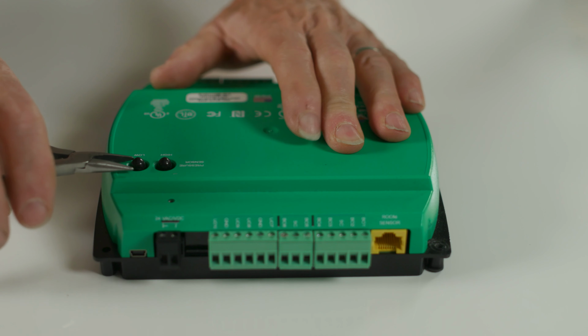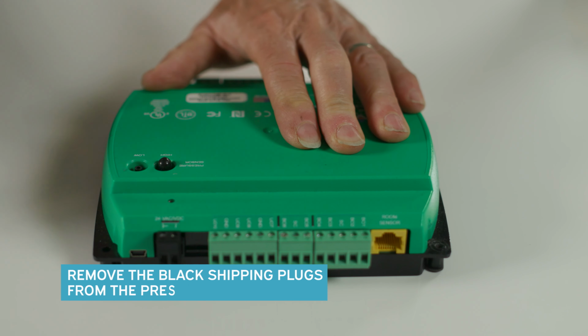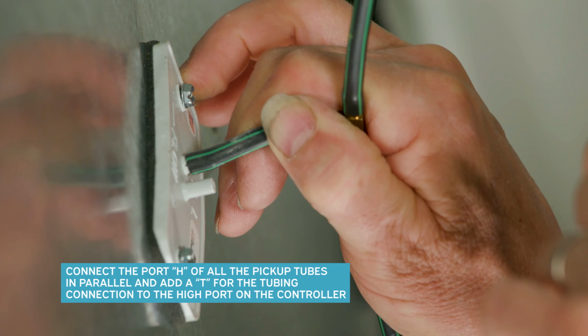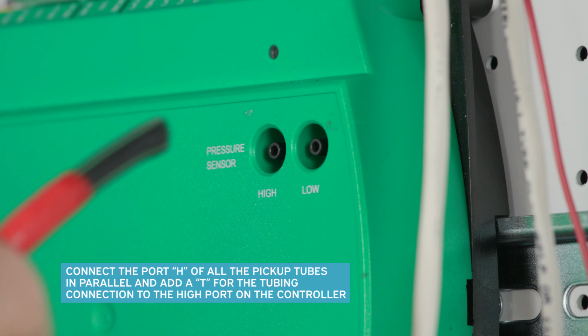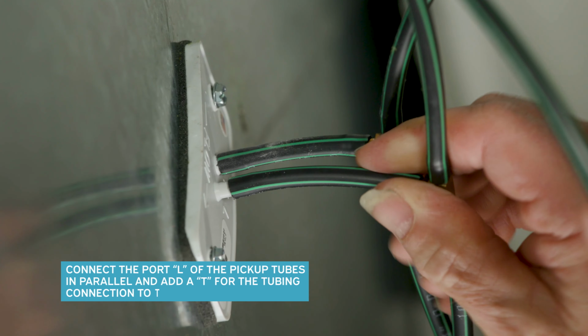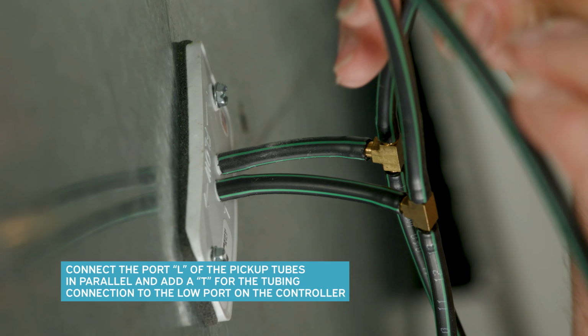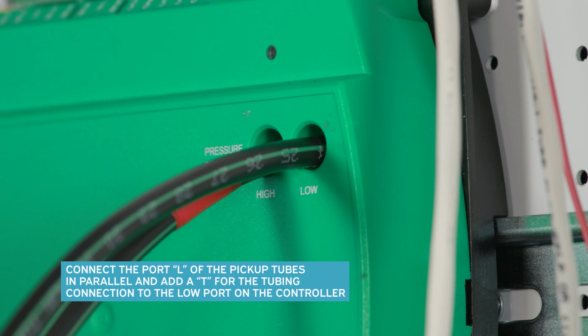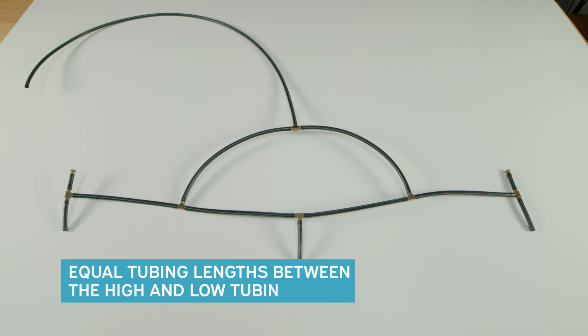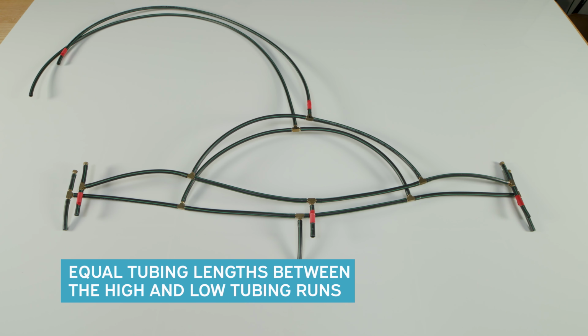If you are using a BAC 9311C AFMS, remove the black shipping plugs from the pressure sensing ports. Then connect the port H's of all the pickup tubes in parallel and add a T for the tubing connection to the high port on the AFMS controller. It is best practice to locate this T in the middle of the manifold. Then connect the port L's of all the pickup tubes in parallel and add a T for the tubing connection to the low port on the AFMS controller. It is best practice to locate this T in the middle of the manifold. It is good practice to have equal tubing lengths between the high and low tubing runs. Also locate the controller and sensors so that the tubing length is minimized.